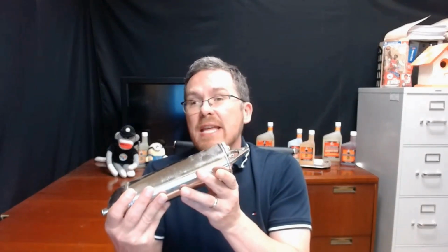Now, speaking of depth, how do you get a fuel sampler to the depth that you need? There are a couple of ways to do that. Now, if you have a conventional bacon bomb like this one, you would use a tank measuring stick to first measure the depth of the tank from the port that you're going to be lowering down. See how far down that depth is. Now, once you have that measurement with your measuring stick, you can mark off on that cord how far down you need to lower it so that it settles in the bottom middle or the middle or 6 inches off the bottom or however you need it to be.